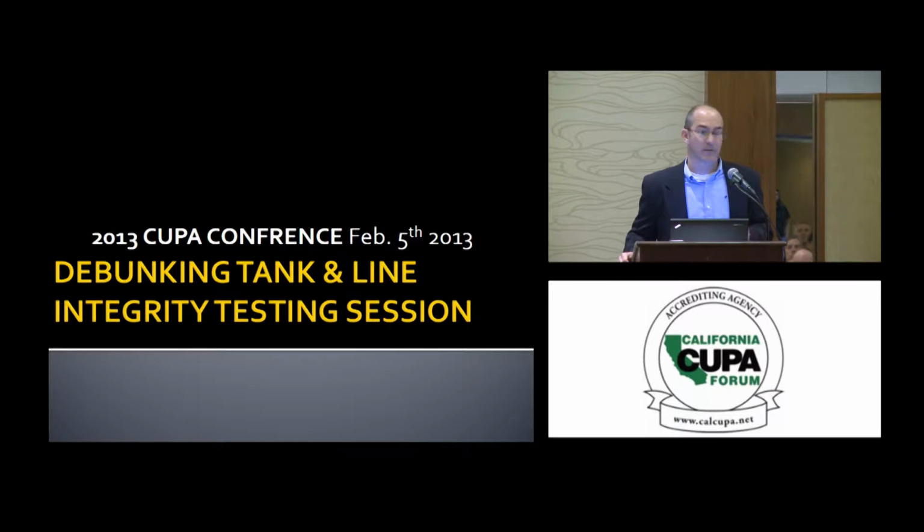The California regulations have two areas; one defines what a tank integrity test is. This is very similar to the tank tightness test requirement: it references 1/10 of a gallon per hour, references a third-party certification, and references the requirement to account for all of the factors in the ground and in the tank. There's one stipulation in California that the tank must be 65% full, which was kind of a unique local requirement.